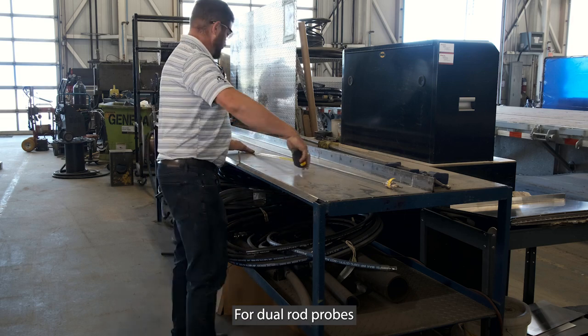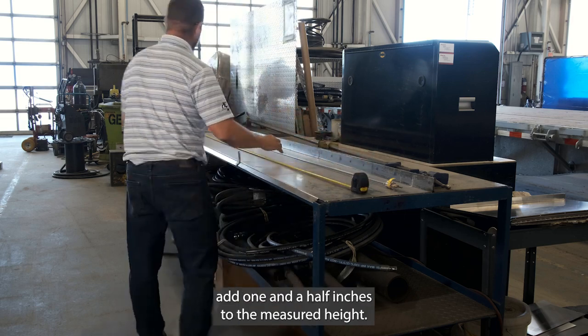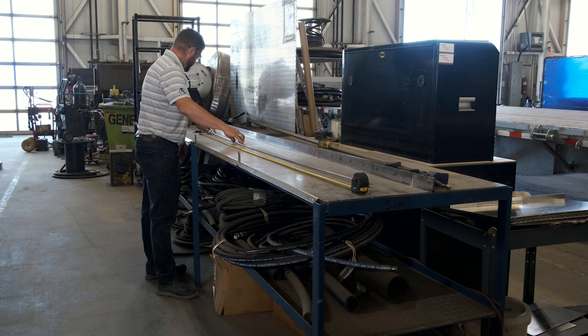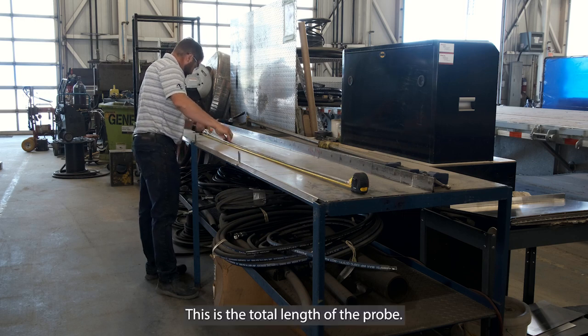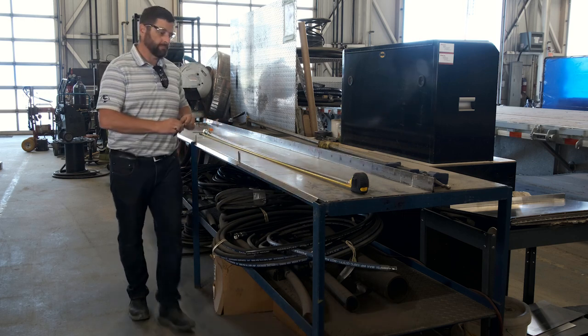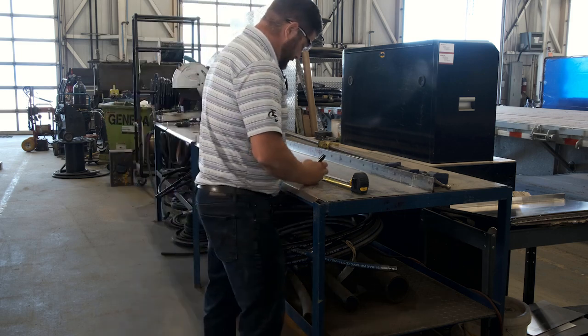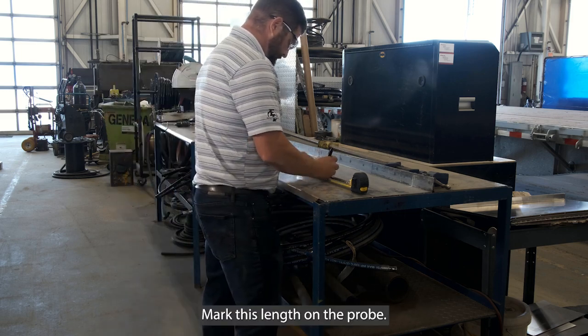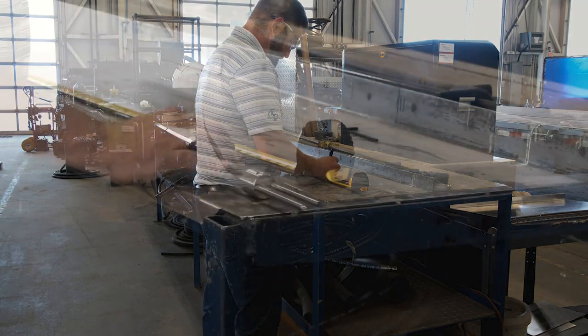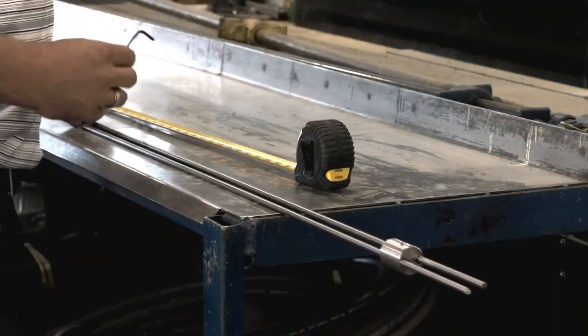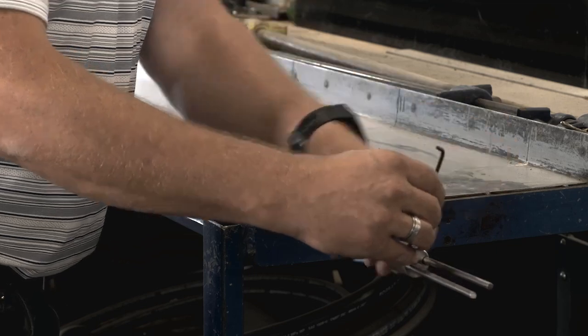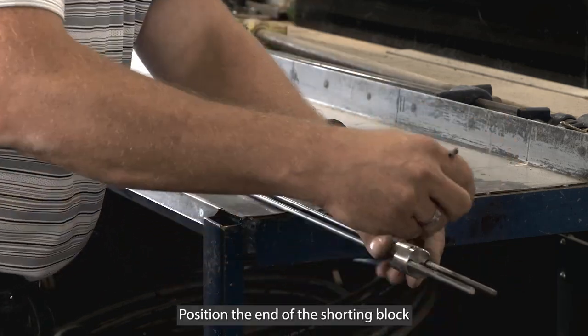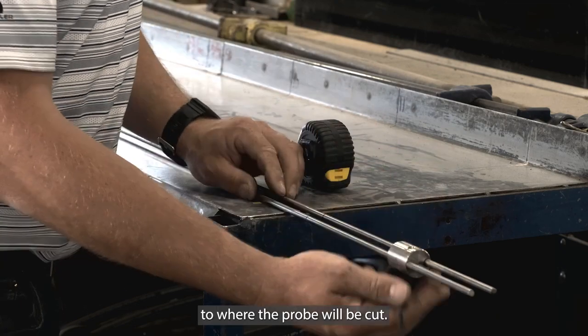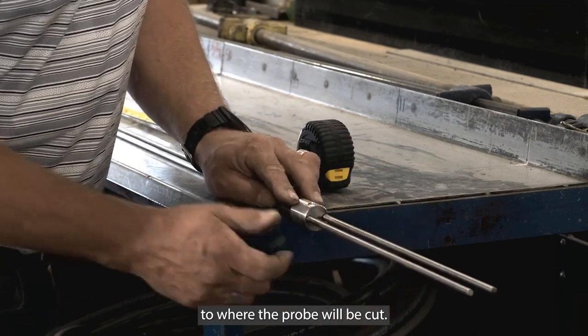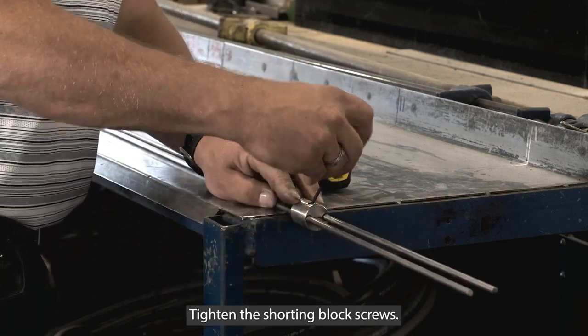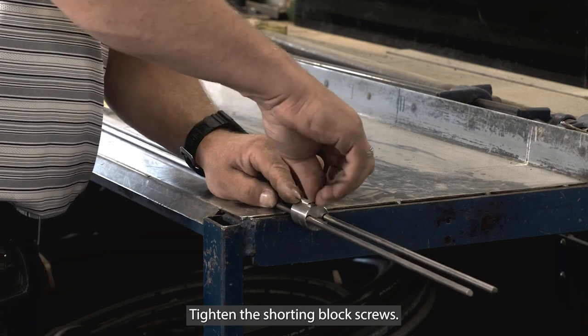For dual rod probes, add 1.5 inches to the measured height. This is the total length of the probe. Mark this length on the probe. Position the end of the shorting block to where the probe will be cut. Tighten the shorting block screws.